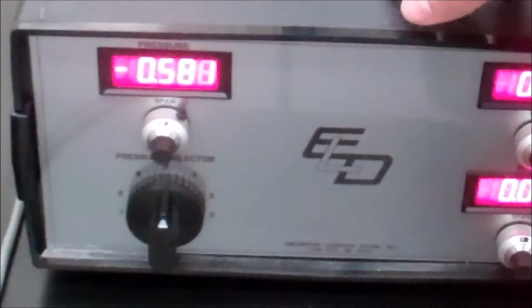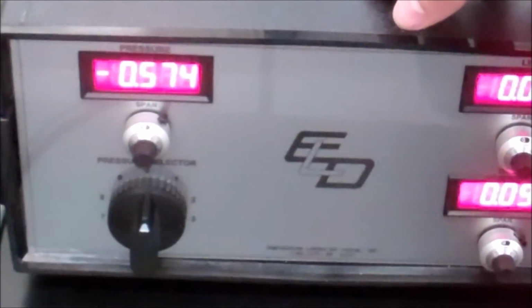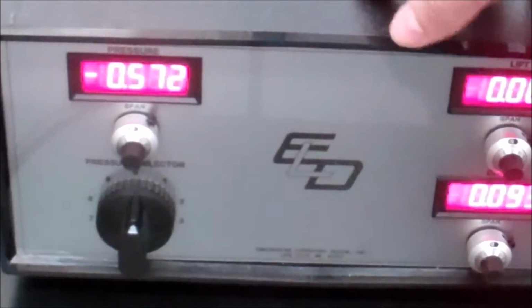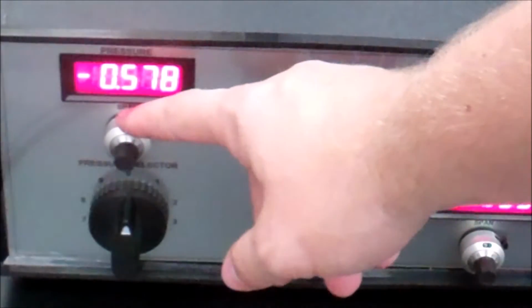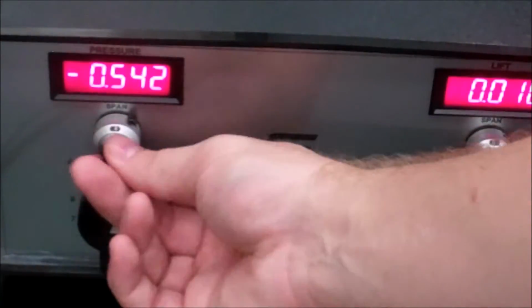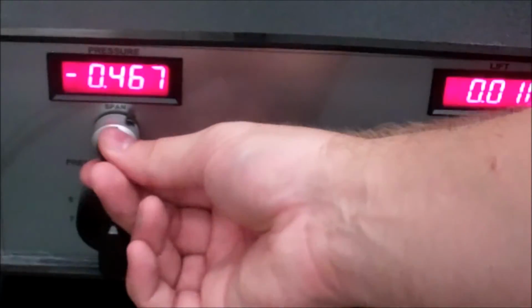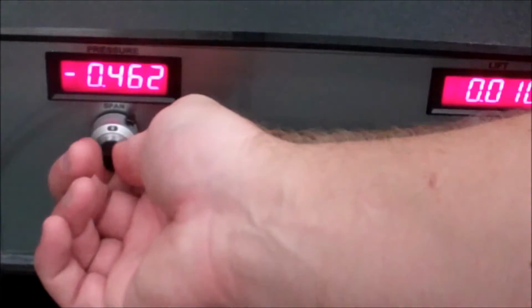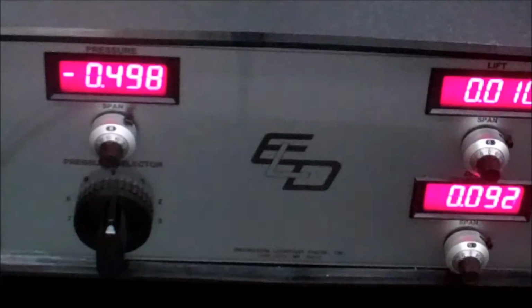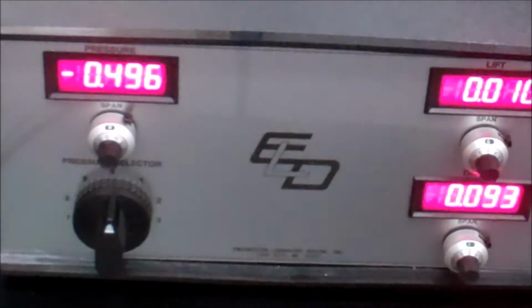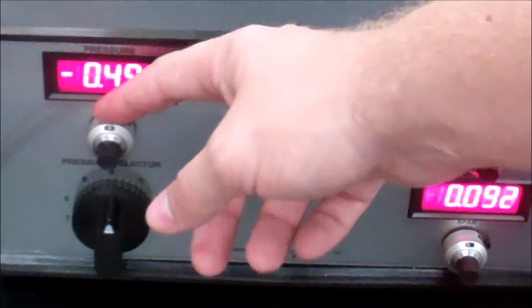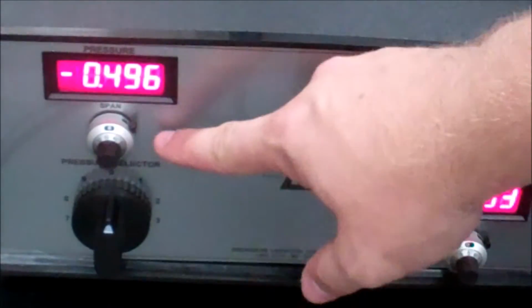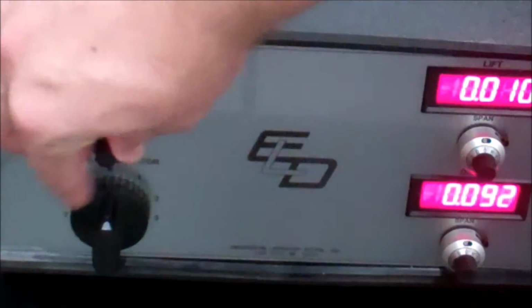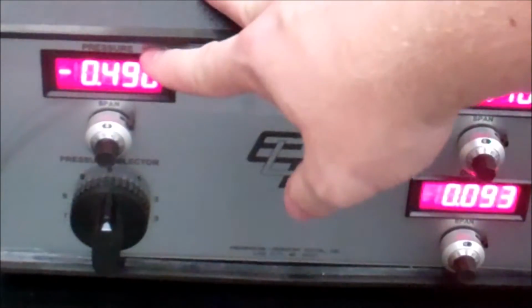Now before you calibrate it, it's recommended to turn the system on and let it set for 15 minutes. Now this span is where you adjust the amplification of the circuit. For the small amplification, you turn the knob to like 0 or 1. But whatever one you're using, do not change it from that once you calibrate it. So once you have it set to the proper amplification you want, you go ahead and lock it by pushing the lever down so it can't turn, and you'll notice the voltage.